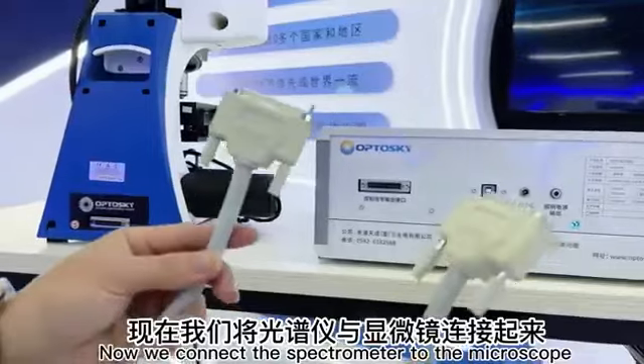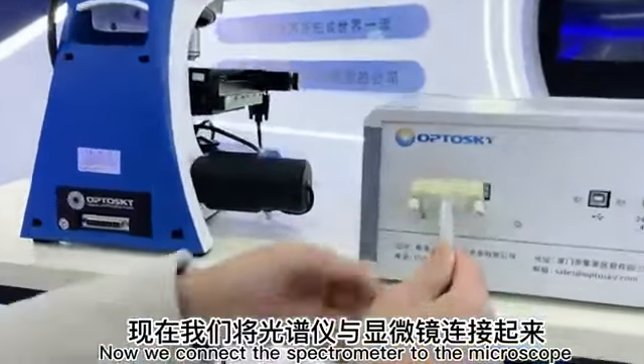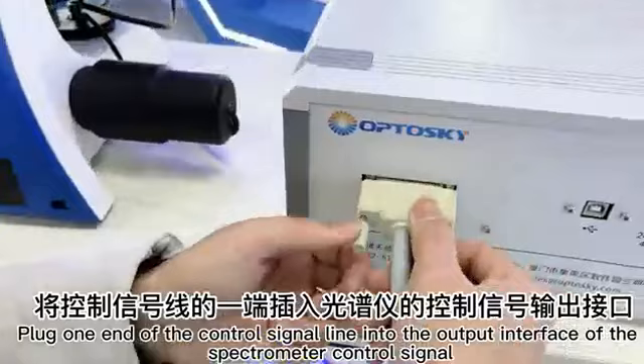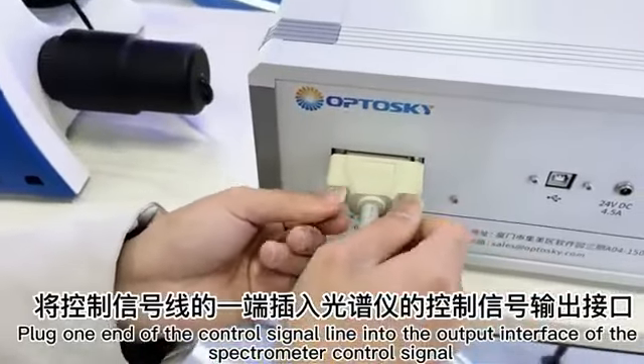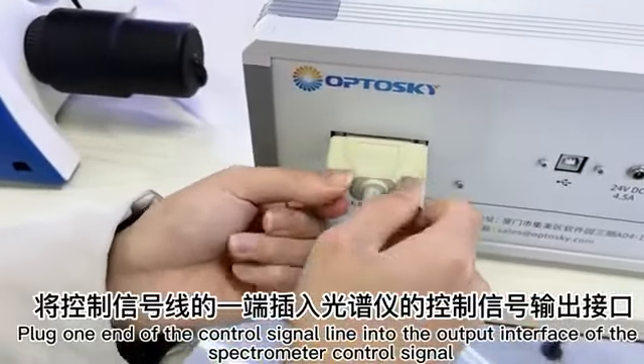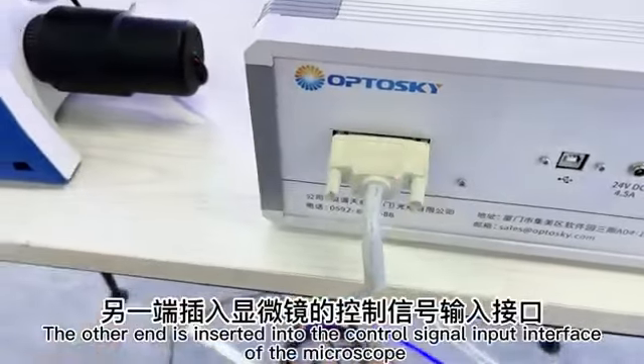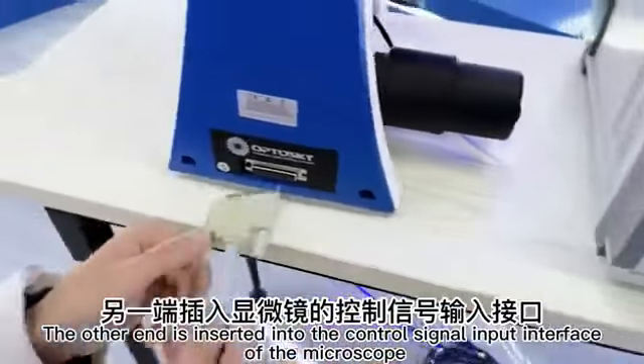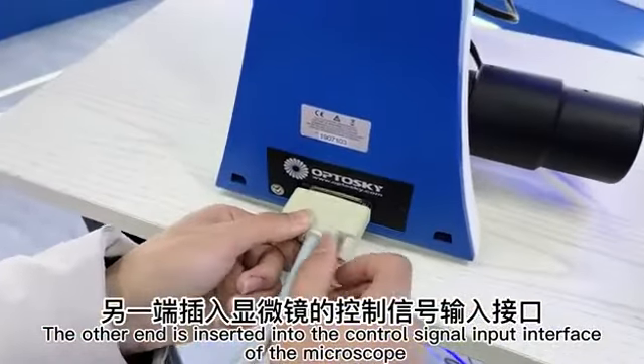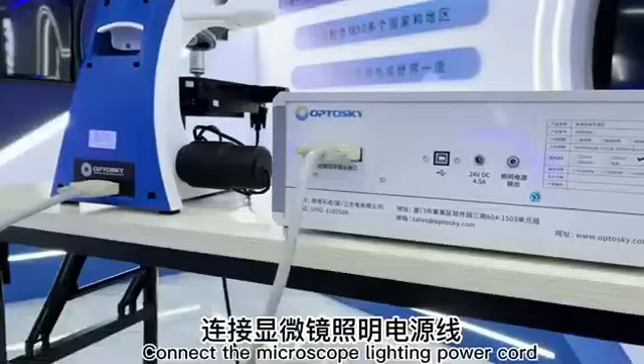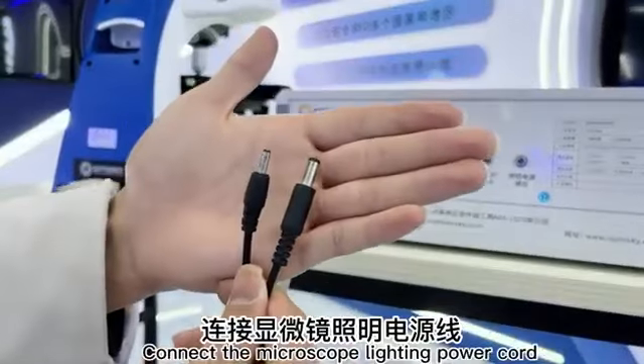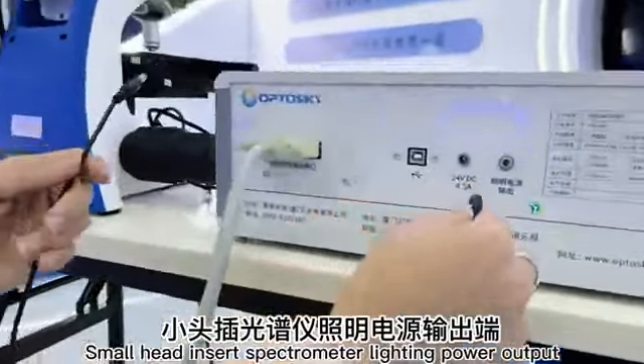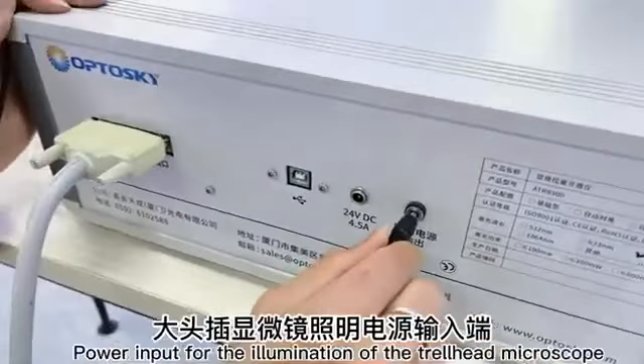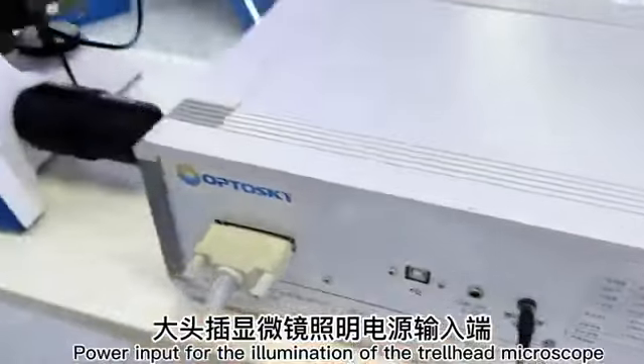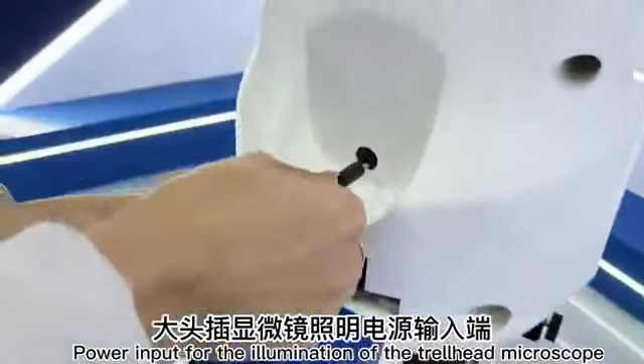Now we connect the spectrometer to the microscope. Plug one end of the control signal line into the output interface of the spectrometer control signal. The other end is inserted into the control signal input interface of the microscope. Connect the microscope lighting power cord. The small head is inserted into the spectrometer lighting power output. The other head goes into the power input for the illumination of the microscope.